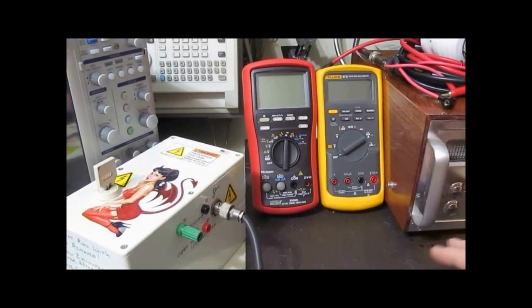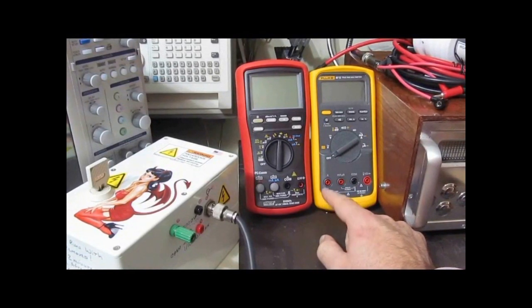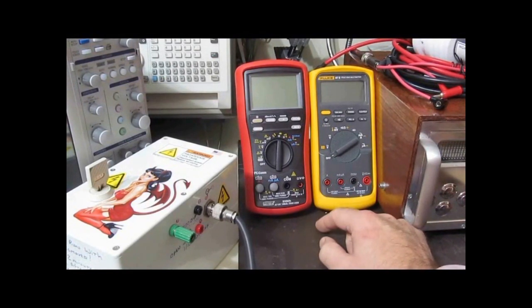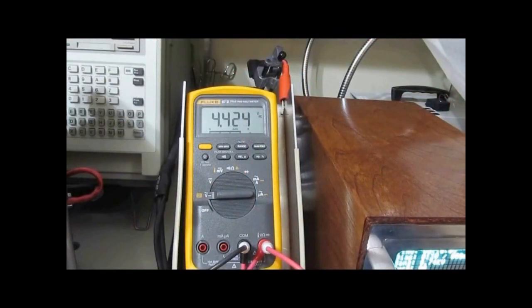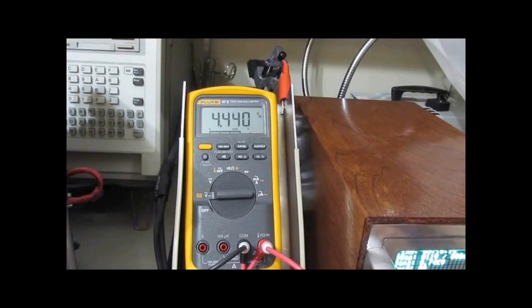My plan now is to use the new generator to test an 87V and try to determine exactly where this meter will fail. I just finished testing the 87V. It appears to be functional after the 1 kV hit. So we'll go ahead and increase this to 1.5 kV.